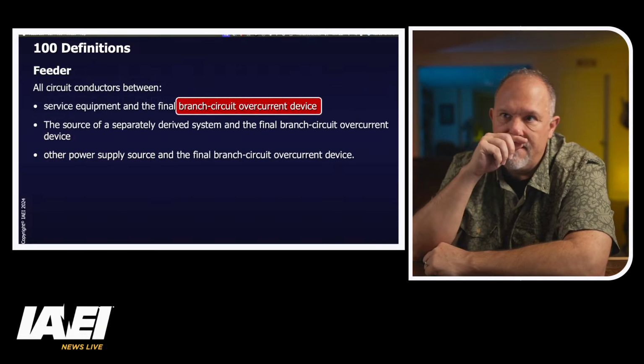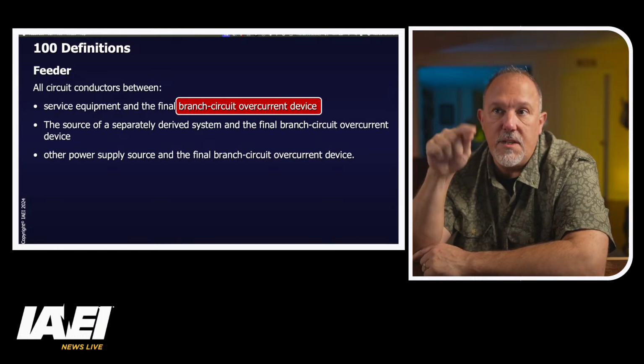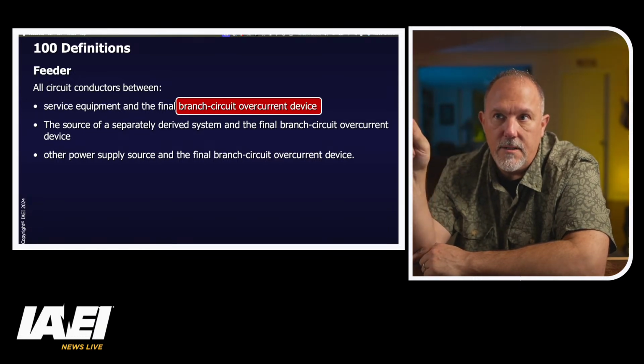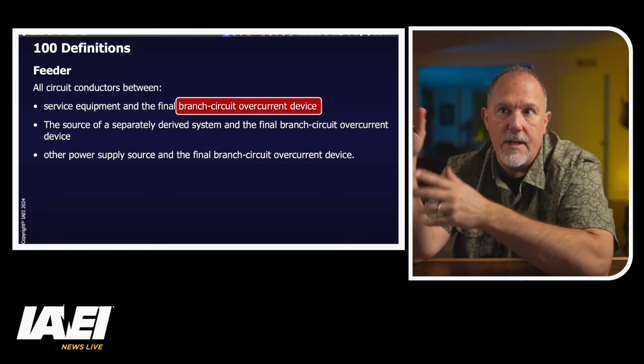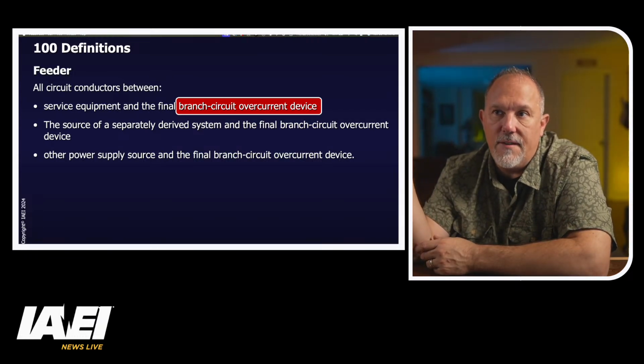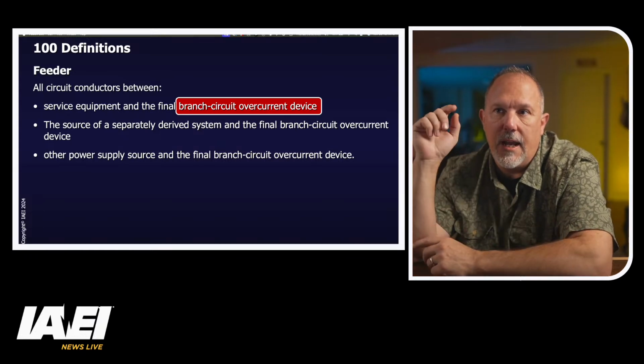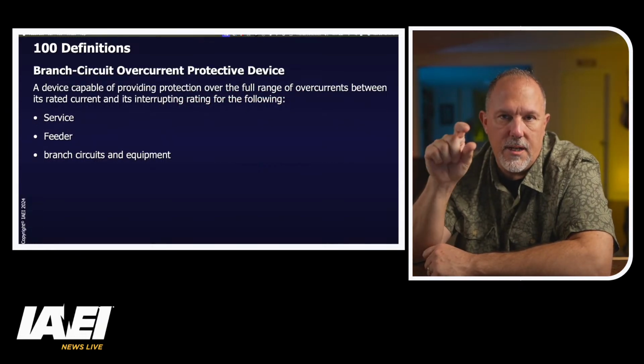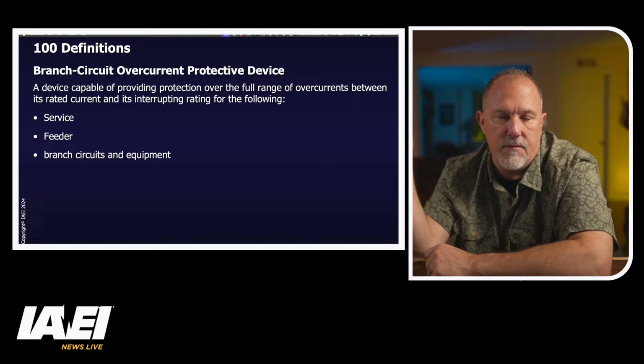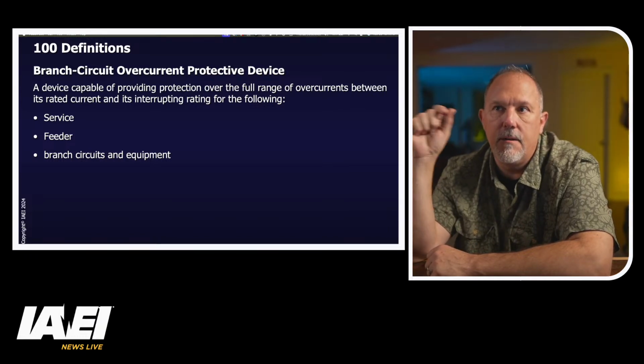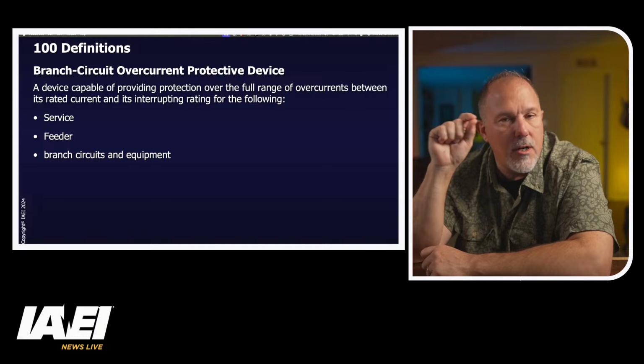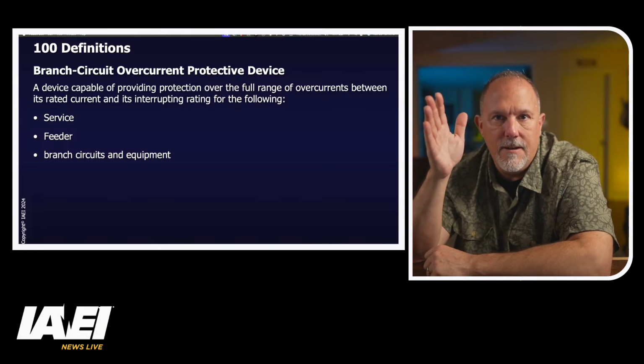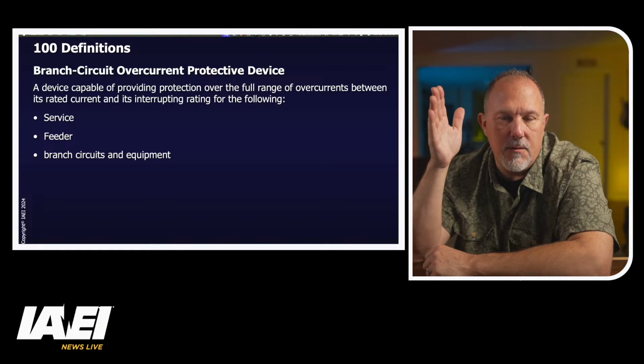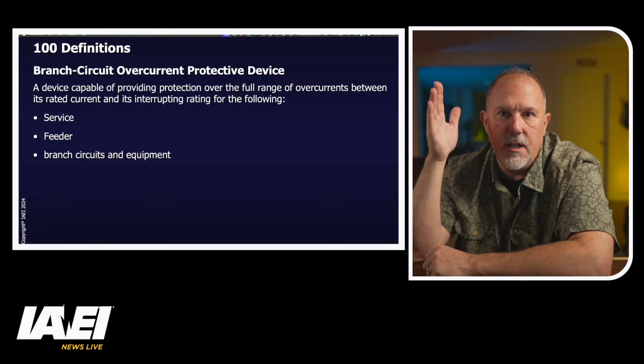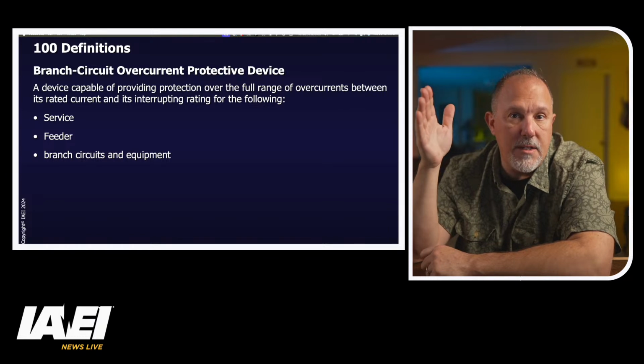Let's go back real quick. All circuit conductors between service equipment and the final overcurrent device, the source of a separately derived system and the final overcurrent device, and an other power supply source. So right now, what we're trying to help you understand is that when we say a branch circuit overcurrent device or a branch circuit overcurrent protective device, we're not talking about a branch circuit. A branch circuit overcurrent protective device can protect a feeder, it can protect a service, it can protect a branch circuit, it can protect equipment.